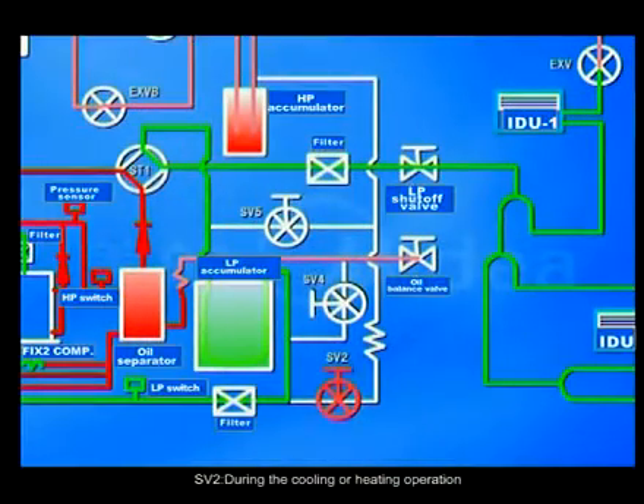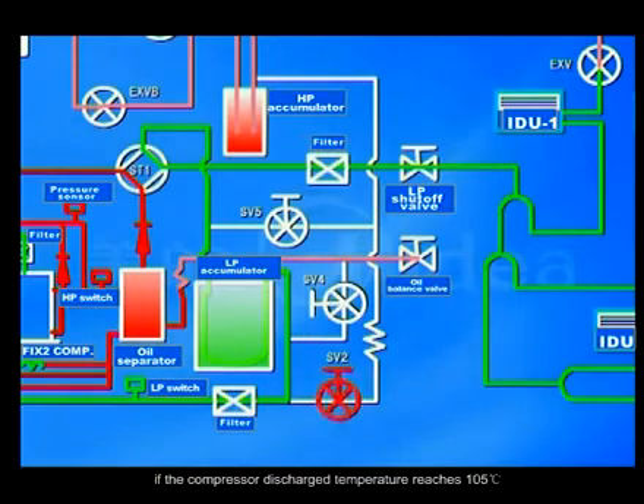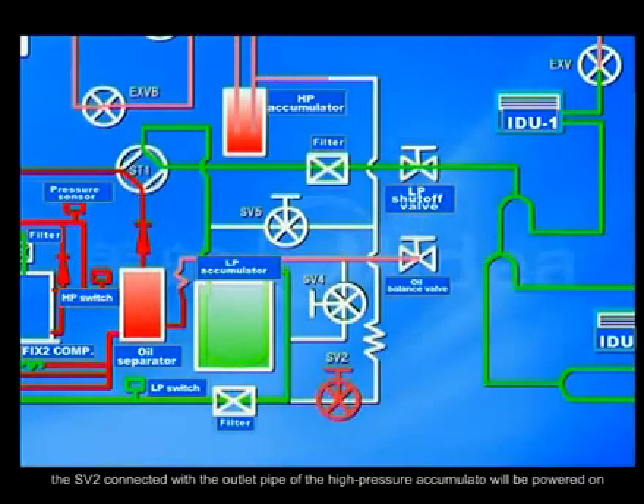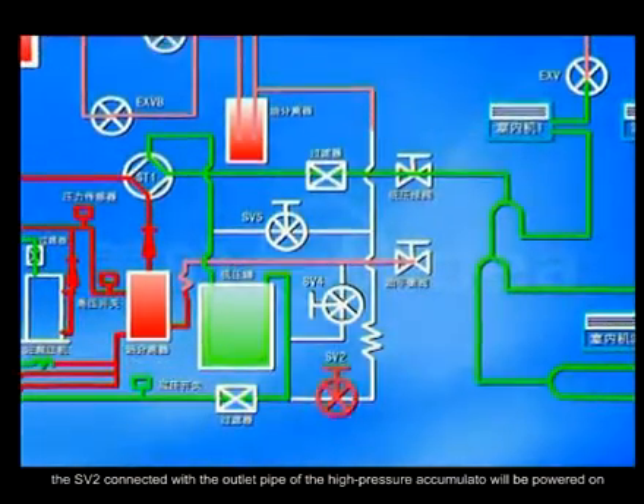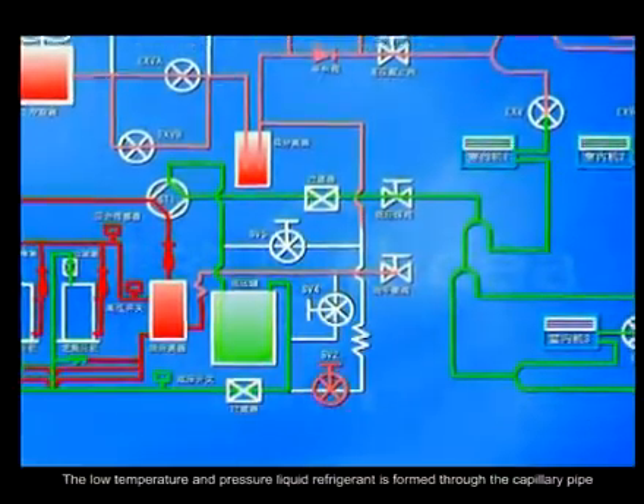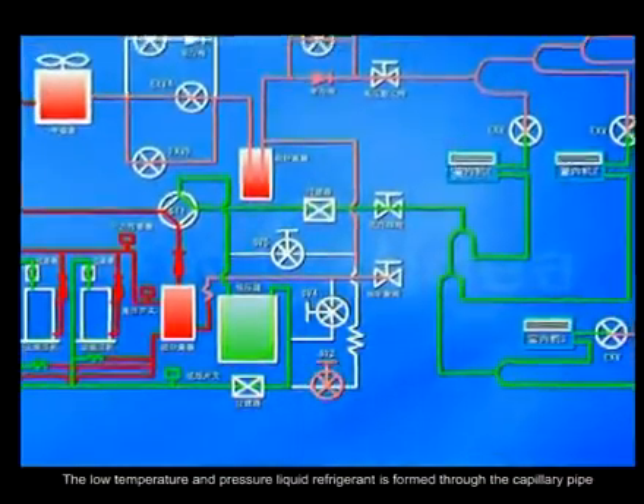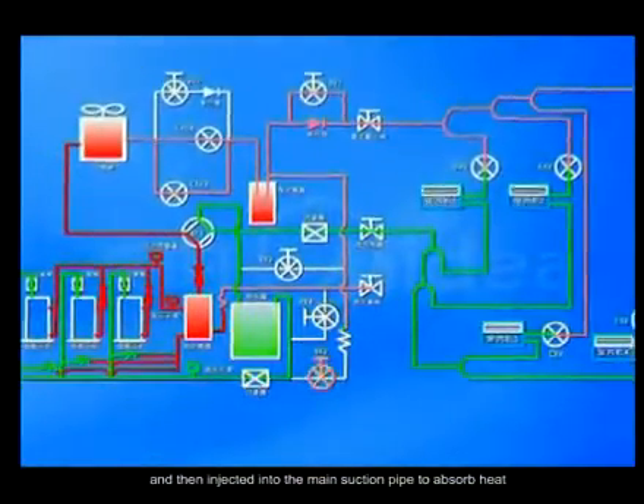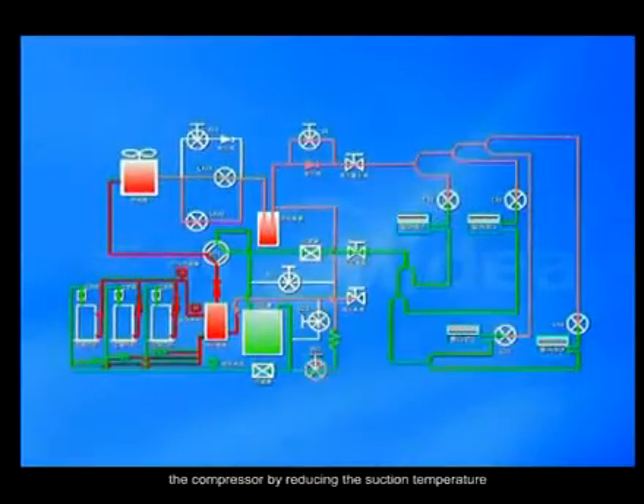SV2. During the cooling or heating operation, if the compressor discharge temperature reaches 105 degrees Celsius, the SV2 connected with the outlet pipe of the high-pressure accumulator will be powered on. The low-temperature and pressure liquid refrigerant is formed through the capillary pipe and then injected into the main suction pipe to absorb heat and increase evaporation, which can cool down the compressor by reducing the suction temperature.